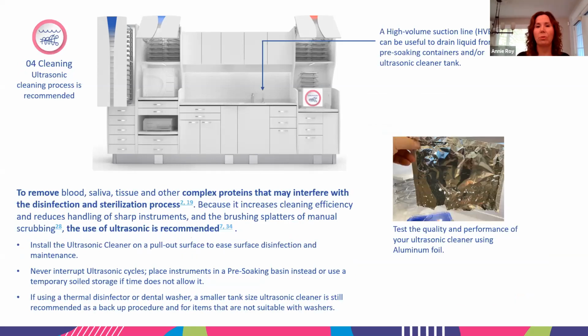So cleaning removes blood, saliva, tissue, and other complex proteins that may interfere with the disinfection and sterilization process. Ultrasonic cleaners should be installed on a pull-out surface to ease surface disinfection of the equipment itself and all around, and to ease maintenance. Like I said earlier, never interrupt ultrasonic cycles.